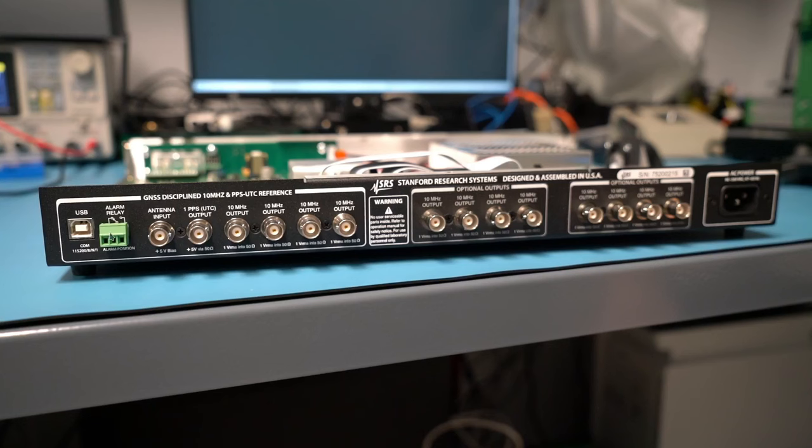Next we have relay outputs with both normally opened and normally closed contacts. I don't plan to use this but if you wanted to have some sort of say a stack light in a calibration lab showing that your time reference shouldn't be trusted or something like that, it is handy to have the ability to trigger external circuitry if your system is losing lock.